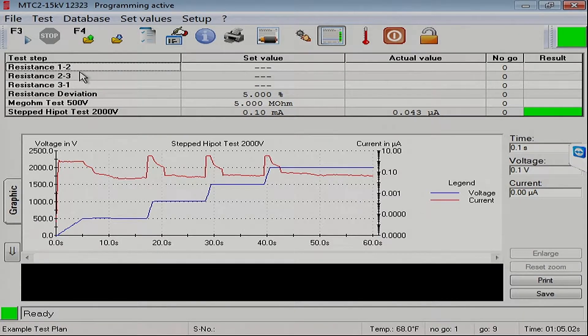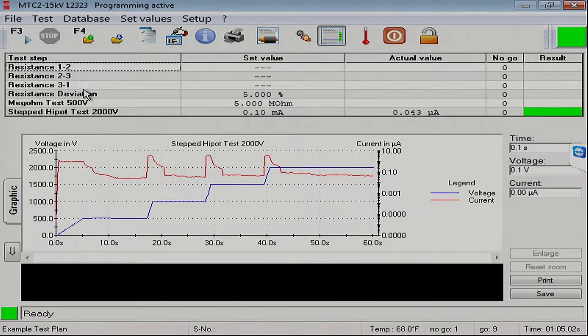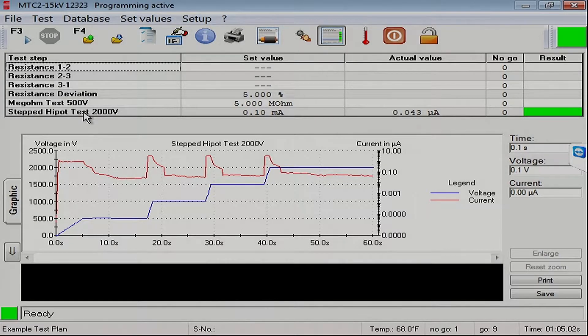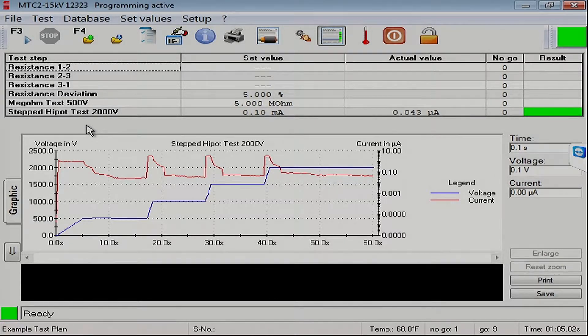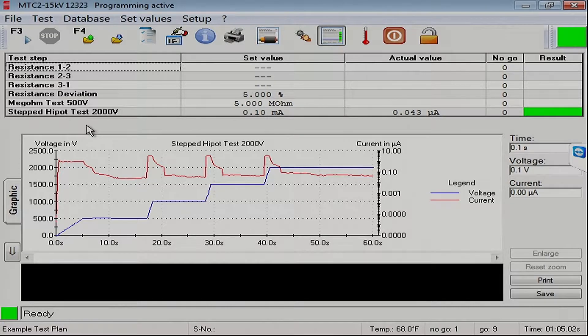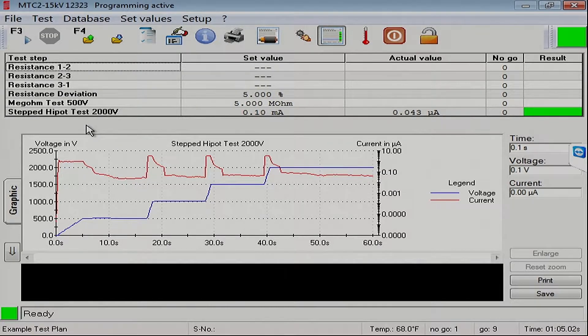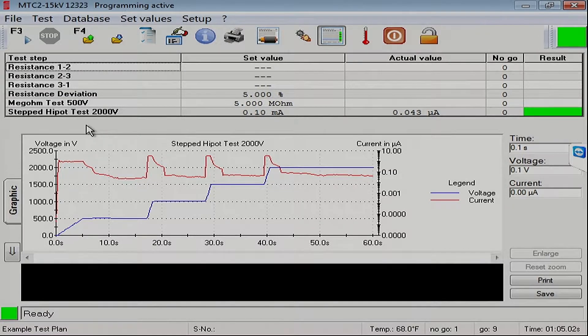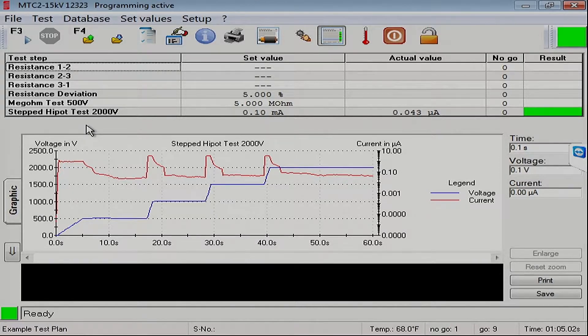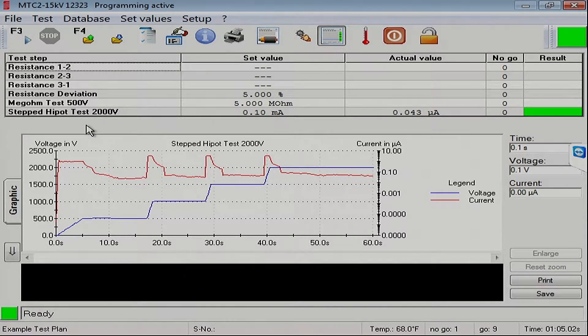As you can see here, we've already set up our resistance test, a megaohm test, and a stepped hipot test. Now we want to add a surge test. What we have connected to the MTC2 right now is a stator, and we'll use a surge comparison test to test that stator.